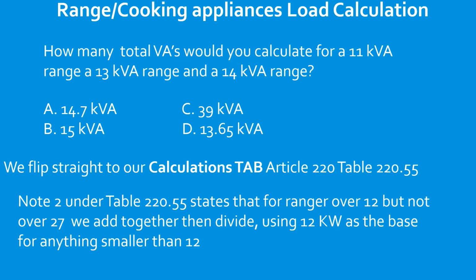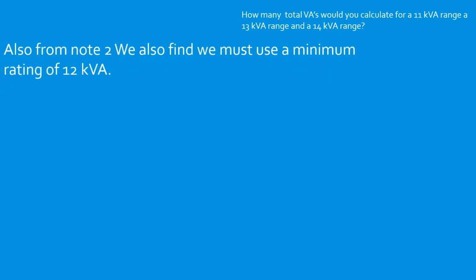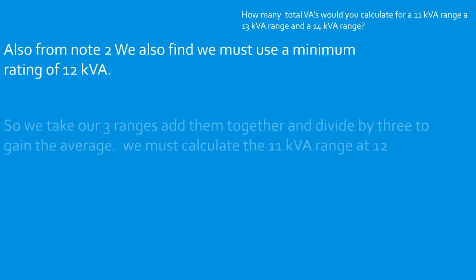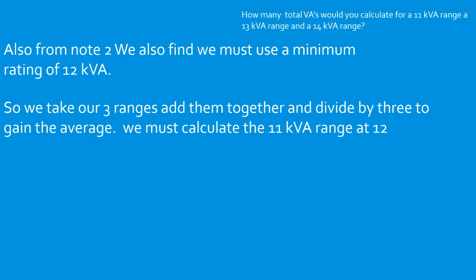Now it sounds kind of complicated, but I'm going to explain it now. All right, so the first thing from note 2, we have to use a minimum of 12 kVA. So we take our 3 ranges, we divide them by 3, and then we treat them as an average, and apply the column C normal method for ranges that are over 12. But we must calculate our little range, our 11 kVA range, at 12.